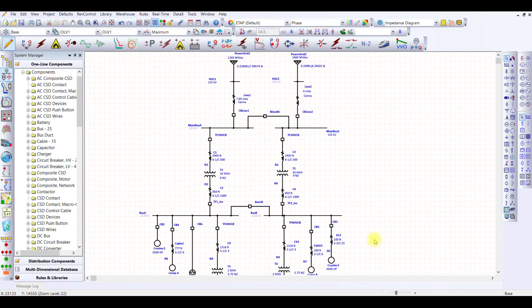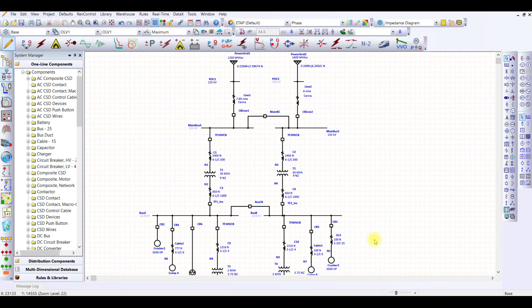For short circuit analysis, we need to perform two kinds of analysis. One is for the maximum fault current and one is for the minimum fault current. When we talk about maximum fault current, we have to select the configuration of the network with the help of which we can get the maximum current. And how can you get the maximum current? Maximum current will only come when you have a system configuration in which the impedance of the network is reduced.